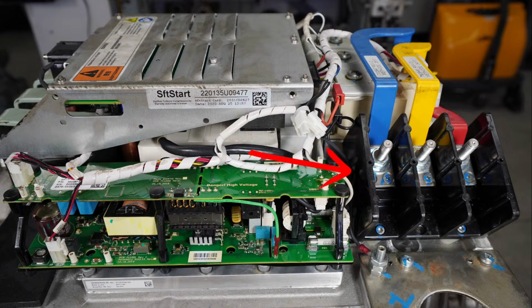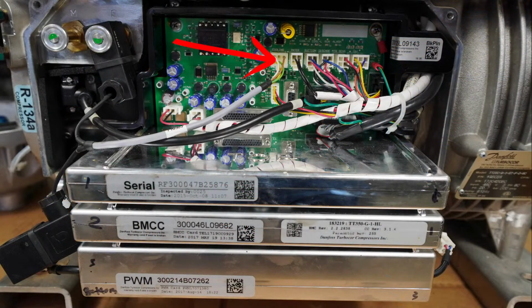So that would be the two directions I would want to go in terms of it's not powering on, it's not showing anything, my backplane board doesn't have any lights. If this is true, even if you have the SMT software, you're not going to be able to plug in and interface with anything. Nothing's going to work. So you're going to have to get this side of the system online if you want to communicate with these modules, talk to this compressor and pull any kind of data.